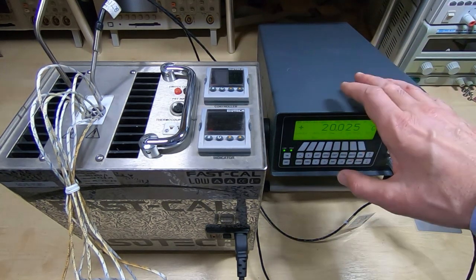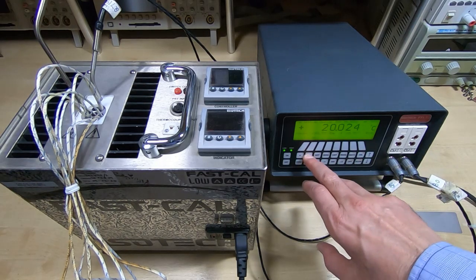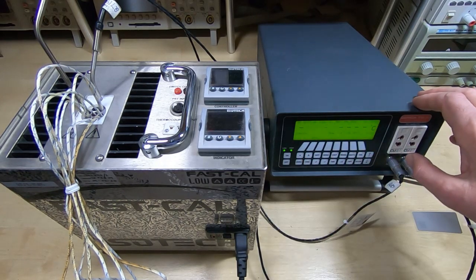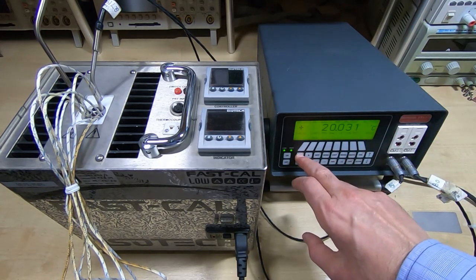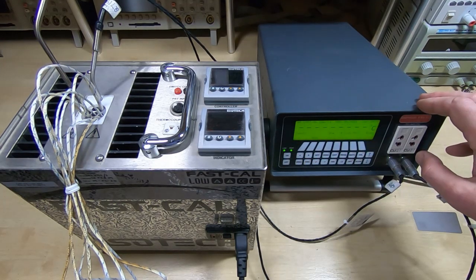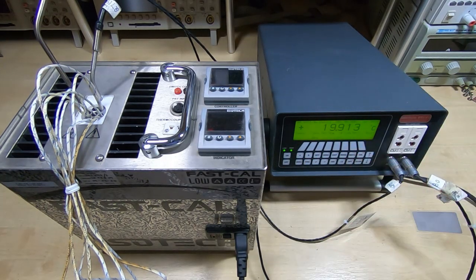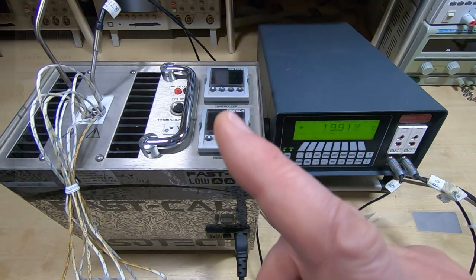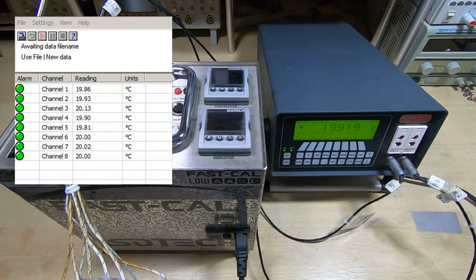Okay, so the temperature's starting to stabilize. We'll check both channels to make sure we're getting an average reading. And so the average here is about 20 degrees, so we'll take a snapshot, and as you can see, again, we are well within the half a degree that we're aiming for.